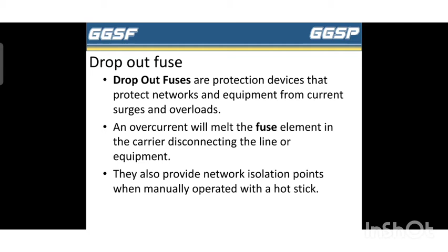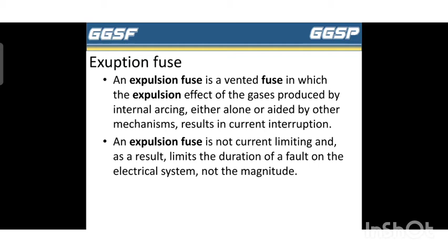Expulsion fuse. An expulsion fuse is a vented fuse in which the expulsion effect of the gas produced by the internal arcing, either alone or aided by other mechanisms, results in current interruption. An expulsion fuse is not current limiting and as a result limits the duration of a fault on the electrical system, not the magnitude.